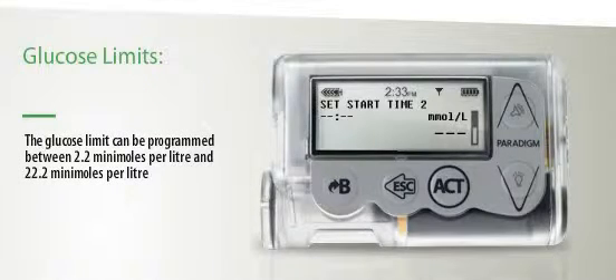Please note, your glucose limits should be different than your overall targeted glycemic control ranges to minimize unnecessary alerts. The glucose limit range can be programmed between 2.2 millimoles per litre and 22.2 millimoles per litre.